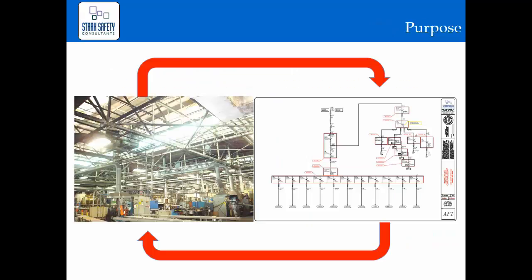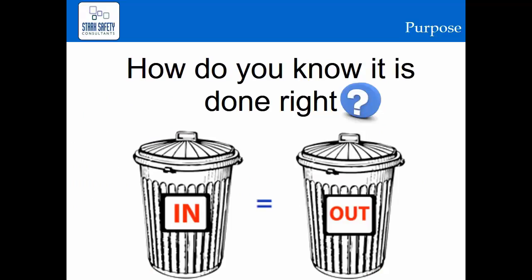This is a very brief review from our previous webinar. Remembering the purpose of doing your arc flash analysis: we are taking representation of the existing field conditions and mapping and modeling it out into a drawing and diagram that we're going to be able to convey the system components as they are in the facility — not as they were intended to be, but how they actually are. Probably one of the worst feelings in the world would be to know that you've done a study, then find out that somebody got hurt because the information you created was not appropriate or accurate and they were injured trying to use that information for safe work planning. When we talk about garbage in, garbage out, we are really focusing on the field data conditions as the most significantly important piece of information — making sure what is in the field is accurately represented.